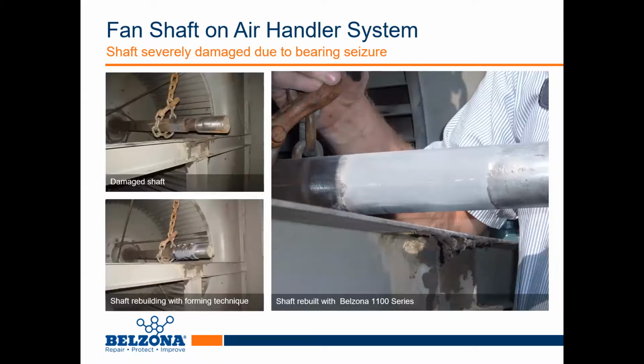So you're going to use a 9411 to prep this shaft, degrease it, and get rid of any oil or any kind of contaminants. Different types of paste grade solutions can be selected depending on the scenario: cure times, how fast you need it back up and running. And then we can fabricate a clamp. This clamp is placed over the shaft. Once that clamp is in, we apply the paste grade material and let it cure.